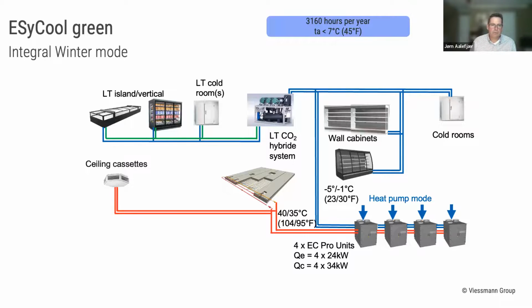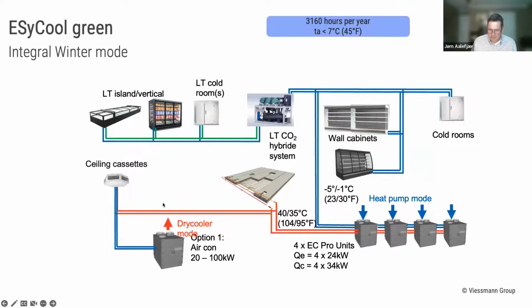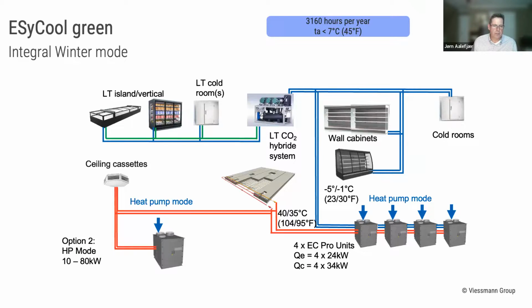Winter mode. This is where we are at our best. So as you see here, it's the same thing here. The heat pump, we are pure heat pump mode on the heat pumps. Using the system as I described. We use the heat into the stores in any way we see fit. And of course, we can use aircon if needed and dissipate the heat out. It doesn't really make sense here. This is the real winter mode where, if there's not enough heat, you can add another heat pump just for heating the stores.